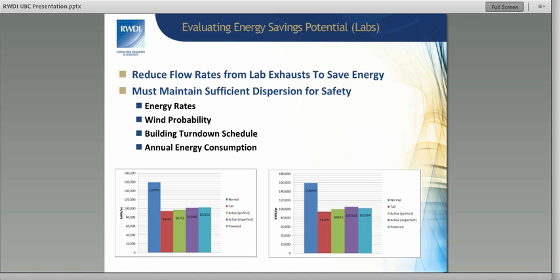As an example, take a lab. During occupied mode, you may have researchers or students using many fume hoods, and the fan pulling air from the hoods and dispersing it outside is running full tilt—that makes sense. But in the evening, in unoccupied mode, sashes are down, nobody's there, minimal flow through the stacks. So do we still have to pump all that airflow and use all that energy we were using during occupied mode?